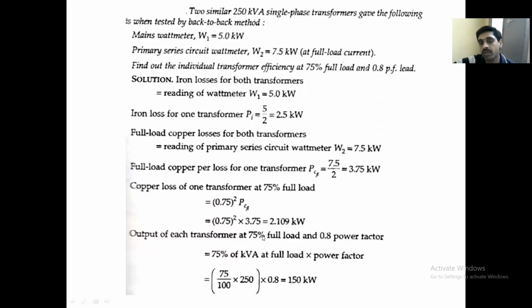Then the output of each transformer at 75% full load and 0.8 power factor is normally V I cos phi. Here I means 75% of the current because it is 75% of the load, and cos phi is the power factor. That's why it is 75% of kVA into 0.8. We will get the output. After getting the output, you can calculate the efficiency equal to X fraction of the full load kVA times power factor divided by X fraction of the full load output plus iron loss plus X square into copper loss. Then you will get 97% efficiency. So this is the way you can calculate the efficiency and regulation when the data is given for Sumpner's test as well as the OC and SC test. Okay.